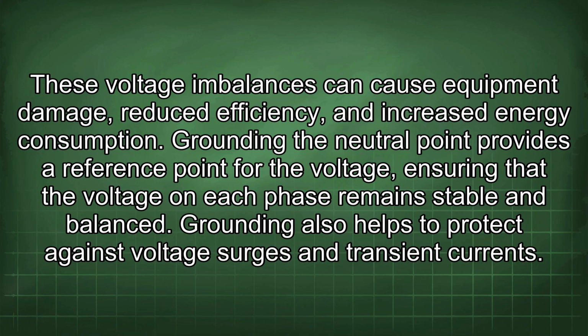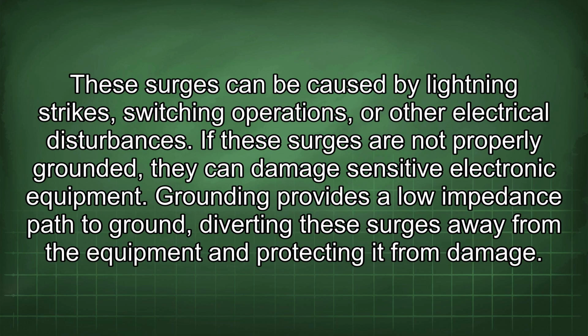and balanced. Grounding also helps to protect against voltage surges and transient currents. These surges can be caused by lightning strikes, switching operations, or other electrical disturbances. If these surges are not properly grounded, they can damage sensitive electronic equipment. Grounding provides a low impedance path to ground, diverting these surges away from the equipment and protecting it from damage.